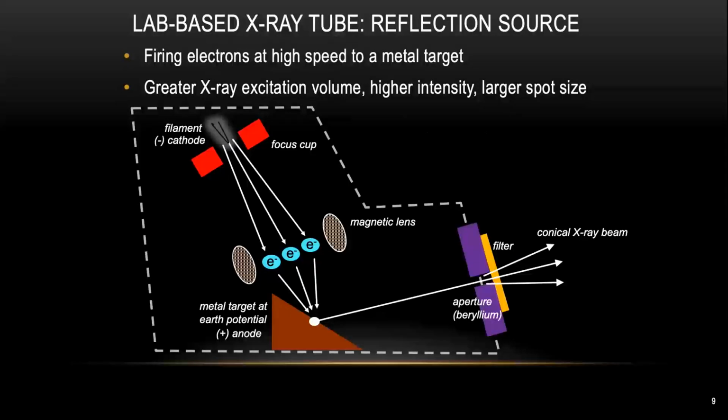So now let's take the first major component we are using in the micro CT machine: the X-ray source. Right now there are two types of X-ray source you can use inside a micro CT machine, and they differ by their geometrical shape. The first one is called the reflection X-ray source.